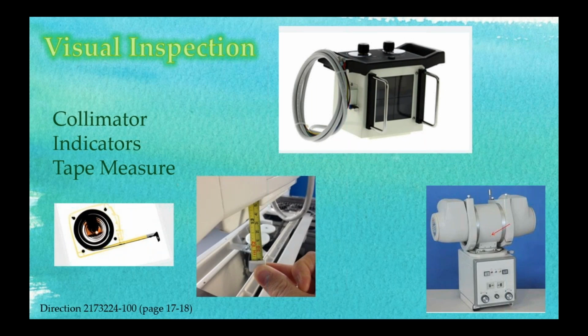Collimator. We do a collimator check, like I just said. We want to see that the light and the x-ray beam are superimposed on one another. There's a little hint here. There's a little red dot or like a little dimple on the outside x-ray tube casing. That's going to signify where the actual radiation begins.